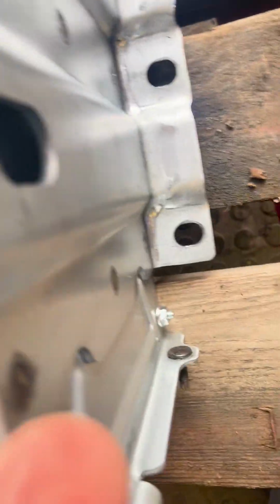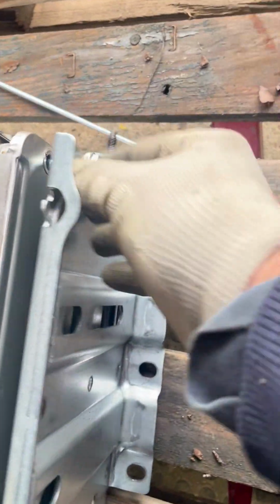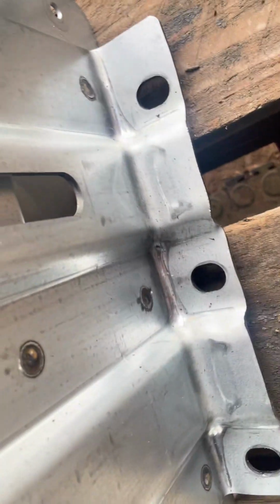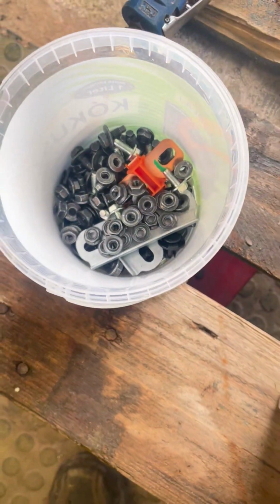The 4 center bolts will come out as well. 1, 2, 3 and 4. That then frees off this last end plate, and beware, the modules will always try and drop down, which is why you don't use a support beam or pallet that's too thin, because if you drop them on the floor there's a good chance you could damage them, and we don't want to be doing that, especially where we're reusing them rather than scrapping them.